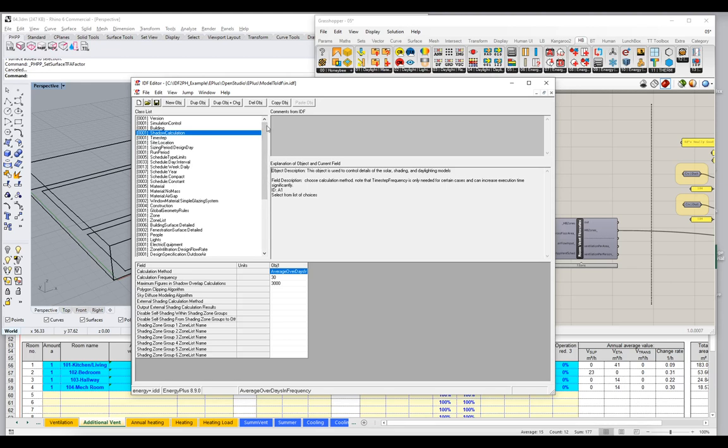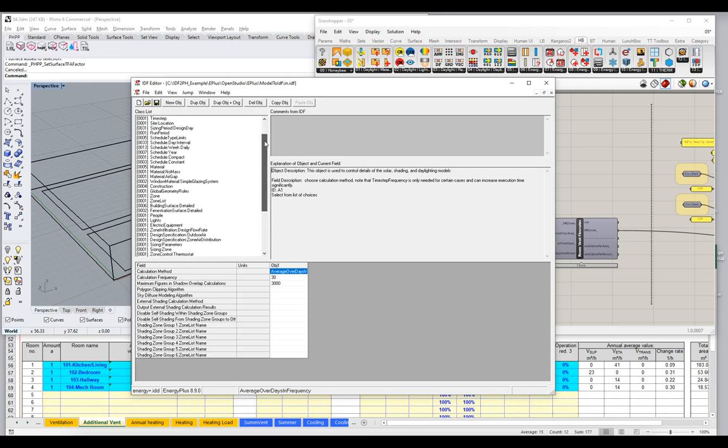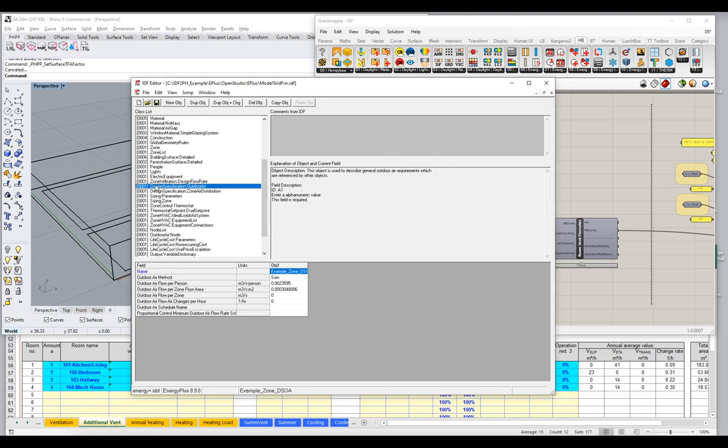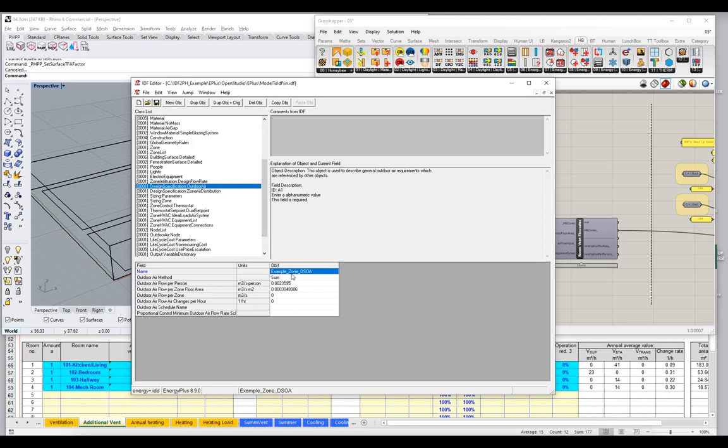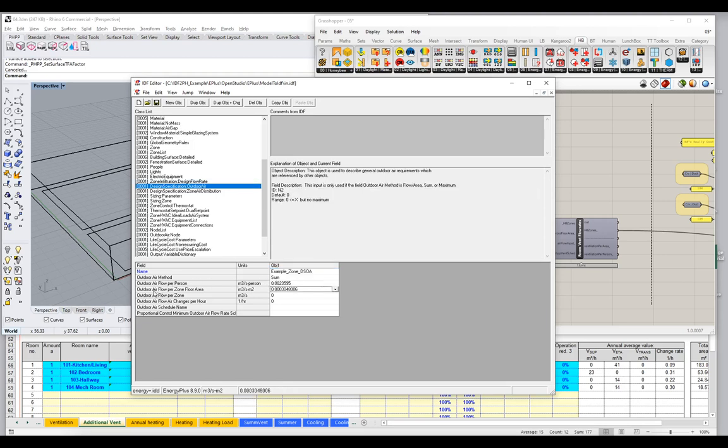So we're interested in the ventilation system. I'm going to scroll down a little bit. And let's see if we can find Design Specification Outdoor Air. So Design Specification Outdoor Air, notice we have one object. And it is the outdoor, the example zone. So that's the name of our zone, outdoor air. And what do we have? We have an outdoor air flow per person, cubic meters per second per person. We have an outdoor air flow per floor area, so per square meter of floor area.